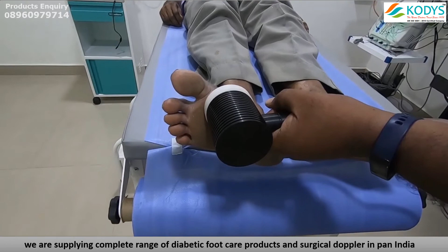Then you have to press this plus button to raise the temperature of the probe. On a prolonged press, the temperature of the sensor will be varied. At a certain point, the patient will feel the heat sensation. Then you have to click this enter. The value gets recorded and goes to the next stage. So the testing of warm perception is completed now. Then we are going to click this save button to complete the testing.